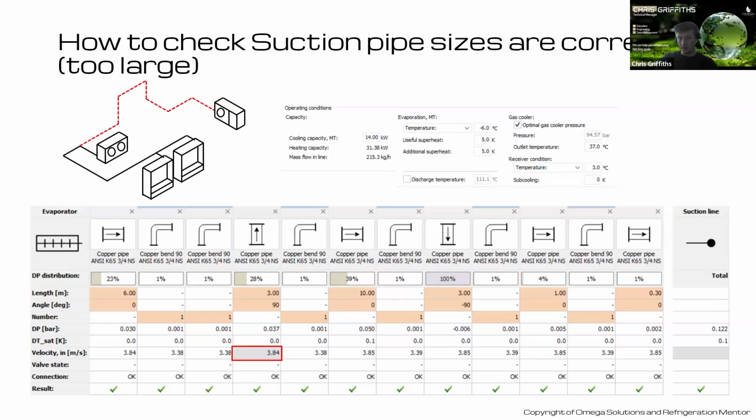I know for HFO designed systems, a similar system to this, I would be probably installing a double riser, because to ensure that velocity can return oil at part load conditions. It's good practice too. But again, model it, make sure you're not getting an excessive pressure drop whilst still maintaining a decent velocity on the system.